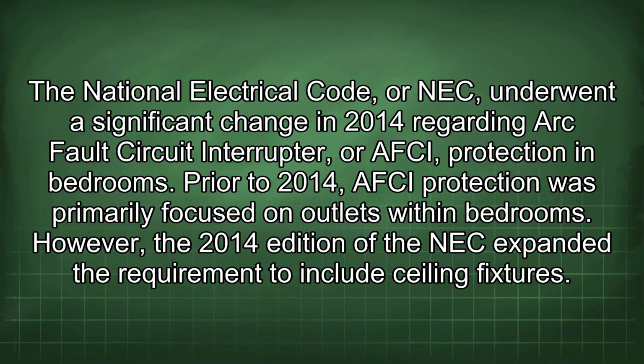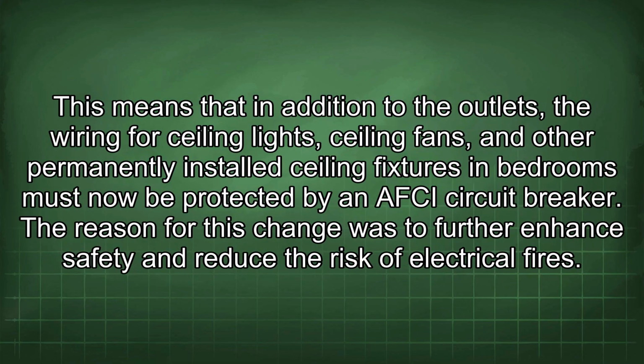The National Electrical Code, or NEC, underwent a significant change in 2014 regarding arc fault circuit interrupter, or AFCI, protection in bedrooms. Prior to 2014, AFCI protection was primarily focused on outlets within bedrooms. However, the 2014 edition of the NEC expanded the requirement to include ceiling fixtures. This means that in addition to the outlets, the wiring for ceiling lights, ceiling fans, and other permanently installed ceiling fixtures in bedrooms must now be protected by an AFCI circuit breaker.